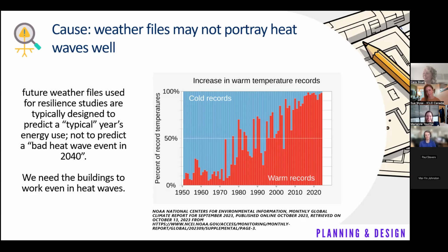So, it is possible with our professional judgment. I still think that the easiest way to evaluate overheat risk, if you have an 8760 model, is actually to take what you think a reasonable heat wave that you want your building to be able to withstand and run that through the model. If you think, hey, I want to make sure that if it's 35 Celsius for 3 days and it only goes down to 27 at night, it does that for 3 days, I want to know what my building does. Just put that in the model, just create that and run it that way.